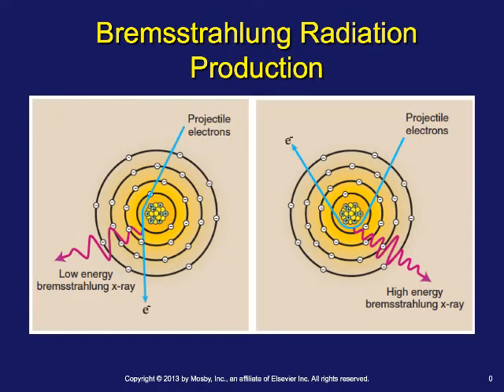Still within the x-ray tube, the first and most important form of x-ray production is Bremsstrahlung radiation. It comes directly from the deep rapid deceleration of the projectile electrons by the high atomic number target — the tungsten target. The arc of the electron's deceleration determines the energy of the x-ray that's produced.